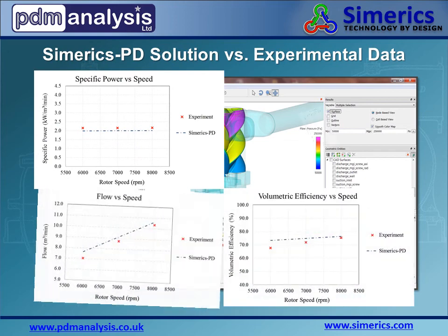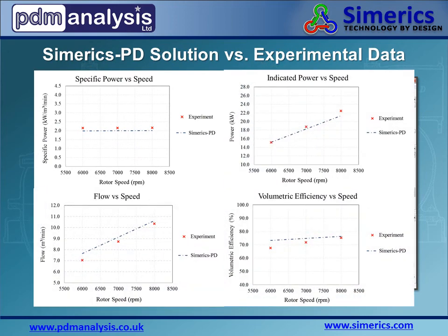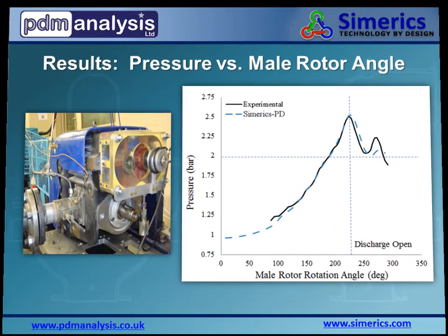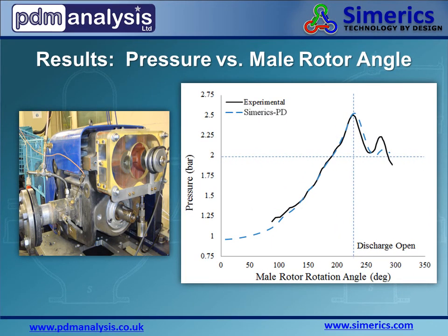These are some of the actual simulation results compared with experimental data collected by City University. Simerics-PD was used like a virtual test stand to predict specific and indicated power, volumetric flow rate, and efficiency as they relate to rotor speed. This chart shows how Simerics-PD was able to capture the pressure magnitude throughout the rotational cycle of the male rotor, with results of particular interest at the 230 degree position where the discharge was fully open.